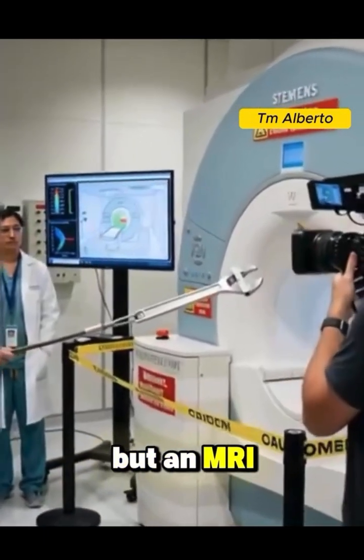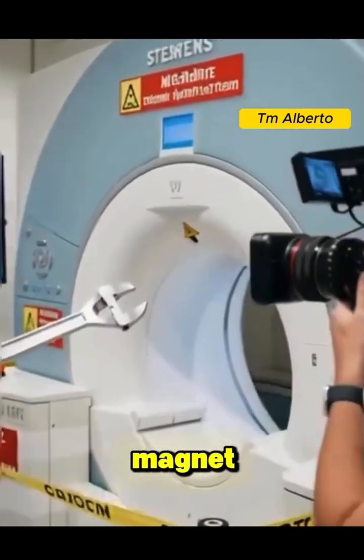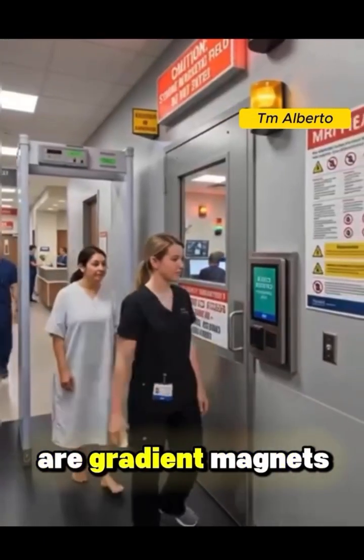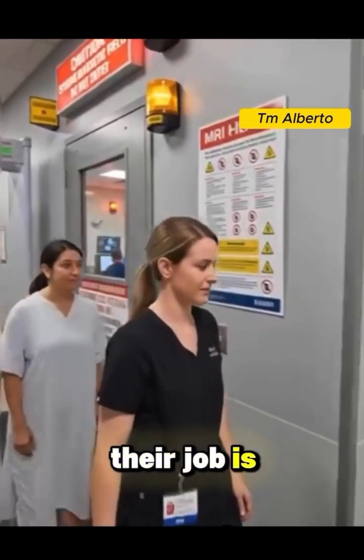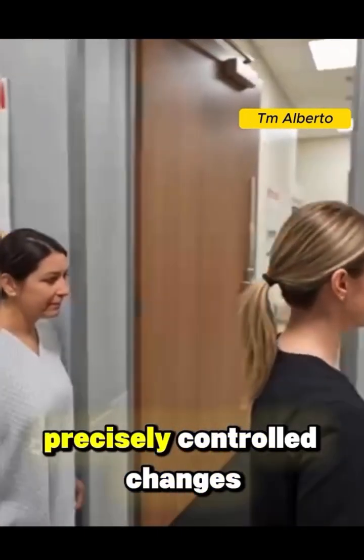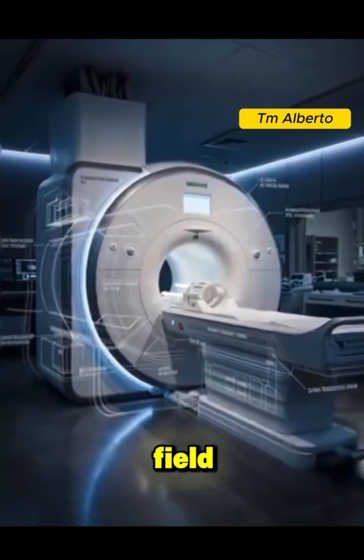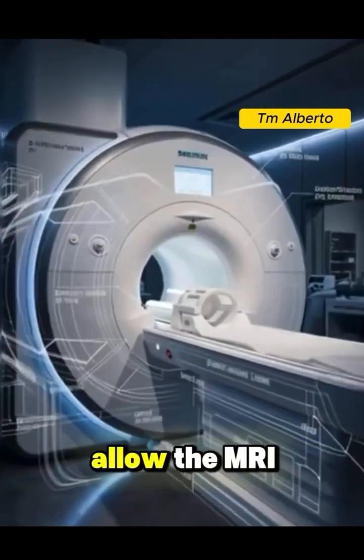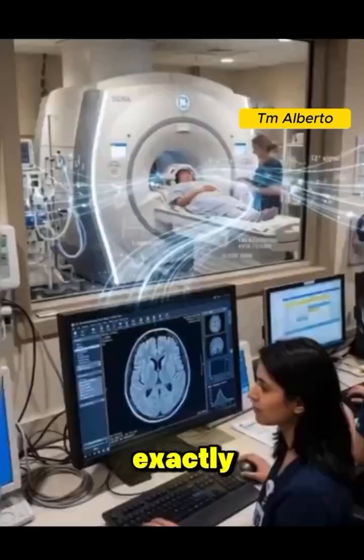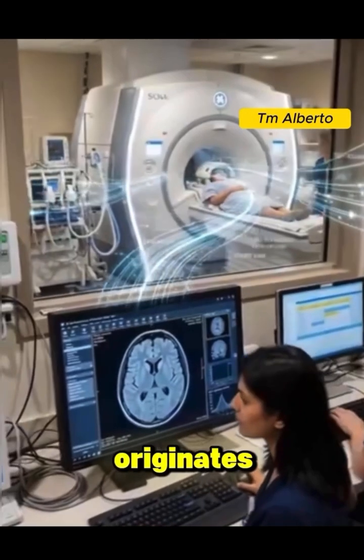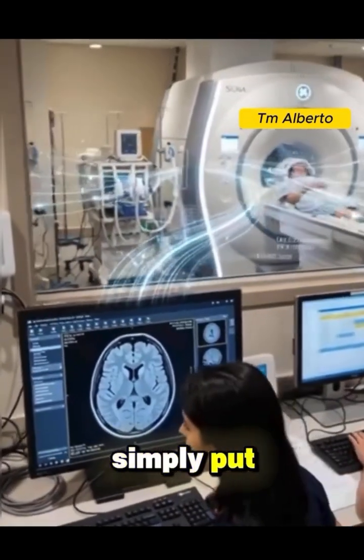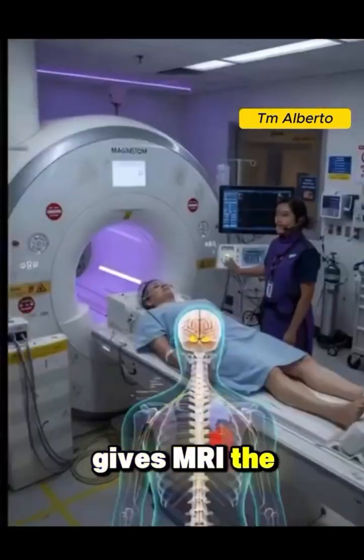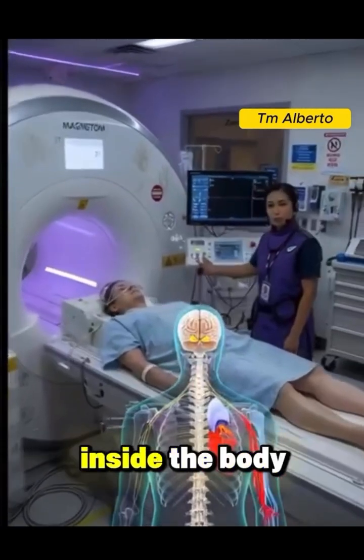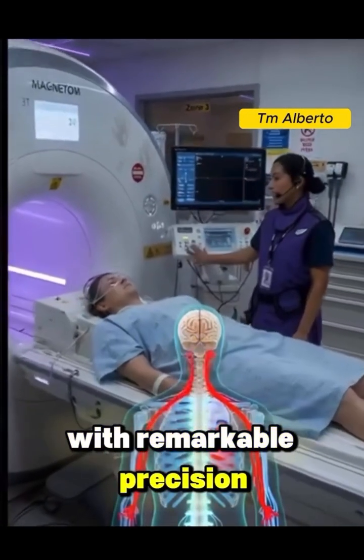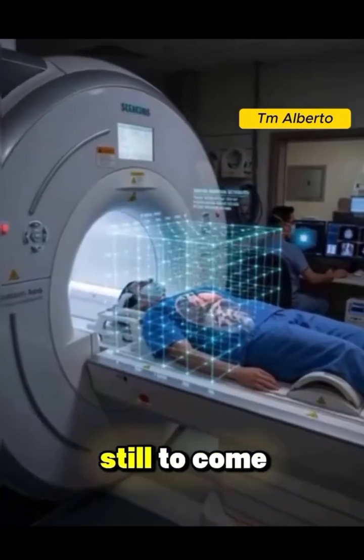But an MRI is much more than a giant magnet. Inside the scanner are gradient magnets. Their job is to create tiny, precisely controlled changes in the magnetic field. These small variations allow the MRI system to determine exactly where each signal originates inside the body. Simply put, this is what gives MRI the ability to locate structures inside the body with remarkable precision. But the most fascinating part is still to come.